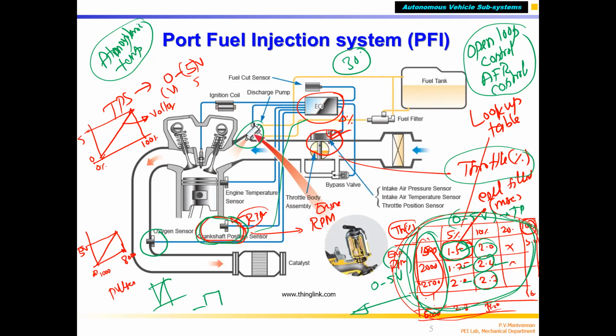You have to set different throttle positions and set the engine speed. The engine should run for a few minutes to stabilize. You cannot take the reading immediately. Change the throttle 5%, the engine goes to some RPM, and you should not take a reading immediately. You have to give a stabilization period to create the map. So we wait 2-3 minutes and see whether the engine is running at 1500 RPM with 5% throttle. You lock the throttle knob, wait a few minutes, and then the engine is in a stable condition.